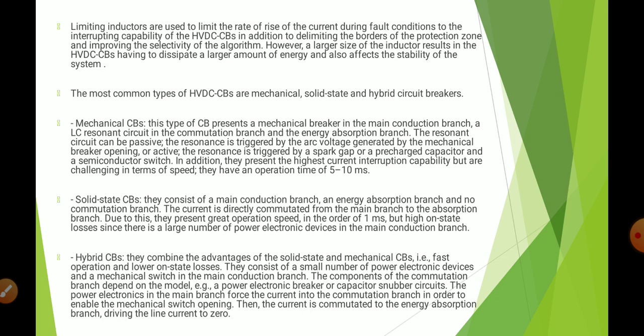Mechanical circuit breakers. It presents a mechanical breaker in the main conduction branch, an LC resonance circuit in the commutation branch, and the energy absorption branch. The resonance circuit can be passive, where the resonance is triggered by the arc voltage generated by the mechanical circuit breaker opening, or active. Thus, resonance is triggered by a spark gap or a pre-charged capacitor and the semiconductor switch. In addition, they present the highest current interruption capability but are challenging in terms of speed and have an operating time of 5 to 10 milliseconds.